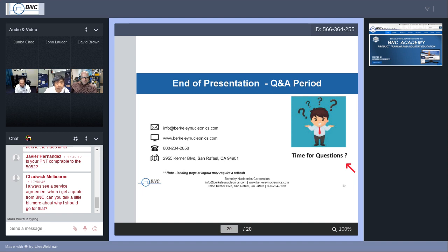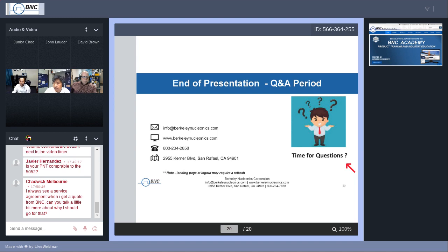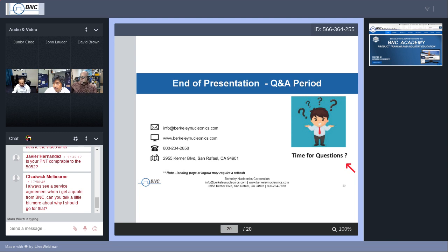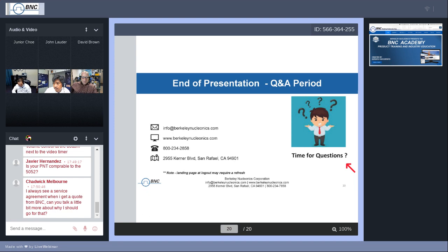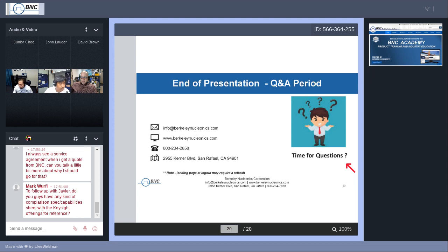You can do a comparison yourself, even side by side, if you have a 5052. I encourage that. My understanding also is that in the ATE modes, our measurement speeds are much faster. Definitely, yes. I'm sorry I didn't mention that. Not only in ATE mode, but in general, our measurement speeds for absolute and additive measurements are quite fast, I would say into the microseconds, depending on the parameters that you have set.